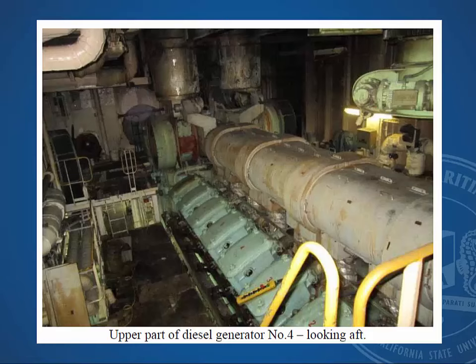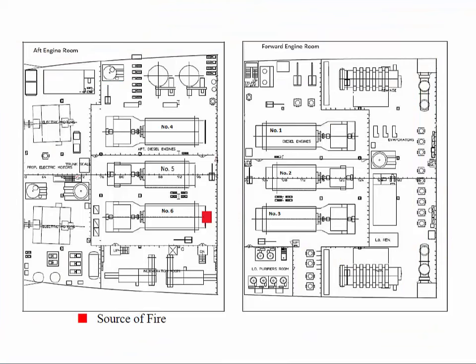So this is number 4, and you can see what a generator would have looked like before the fire. The other thing I want to point out is that you have 6 generators, 1, 2, 3, 4, 5, 6, and 2 engine rooms, an aft and a forward. The source of the fire was right around here in number 6. So only these 2 generators were damaged by the fire. But unfortunately, on the forward engine room, the power cabling from these generators was in this overhead, and it burned, and so they lost all their generators.